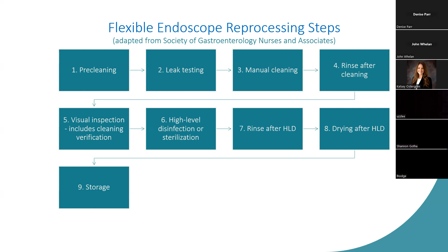Important points for the first step, point of use treatment and pre-cleaning. It's now called point of use treatment to reflect all the work that's done at the bedside immediately post-procedure. We used to refer to it as pre-cleaning, but pre-cleaning is still done. It's just part of the point of use treatment. In pre-cleaning, it's that initial removal of organic material that's critical to make sure we decrease the bioburden load for the subsequent steps. Pre-cleaning has to occur because it's in the IFU, and it should be in your policies that it occurs. And it has to occur as soon as possible after the procedure at the bedside in the procedure room. We need to follow all the steps of the IFU.